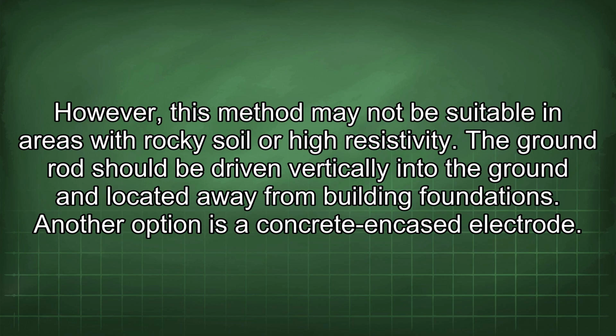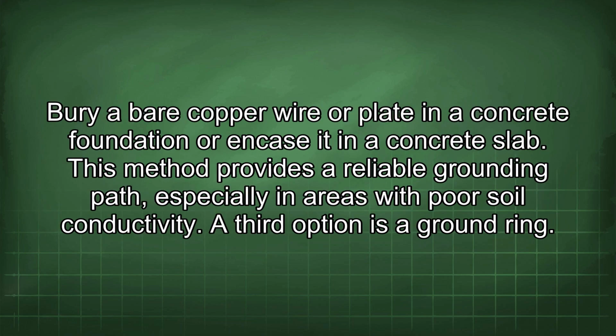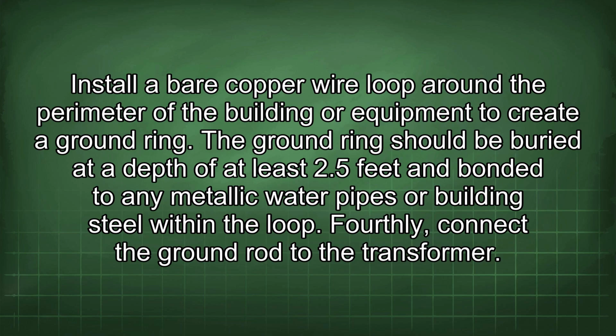Another option is a concrete-encased electrode. Bury a bare copper wire or plate in a concrete foundation or encase it in a concrete slab. This method provides a reliable grounding path, especially in areas with poor soil conductivity. A third option is a ground ring. Install a bare copper wire loop around the perimeter of the building or equipment to create a ground ring. The ground ring should be buried at a depth of at least 2.5 feet and bonded to any metallic water pipes or building steel within the loop.